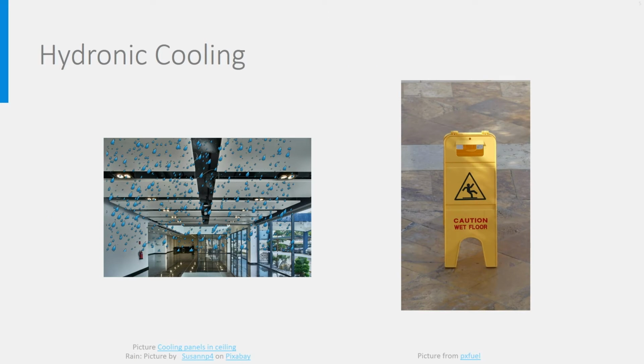The main problem with hydronic coolers is the occurrence of condensation if they are not well designed. If the room air is humid and the chilled water in the ducts is cold, it may be that the air comes below its dew point when flowing along the panel or the floor and then condenses. That's why these systems should always have a dew point temperature control, switching the cooling system off when approaching the dew point.